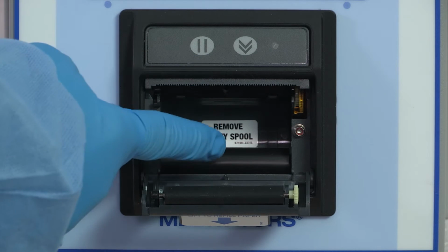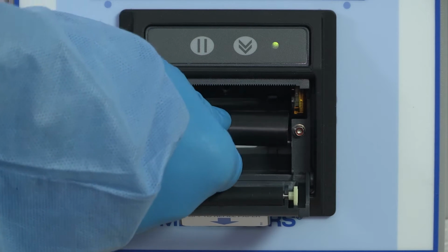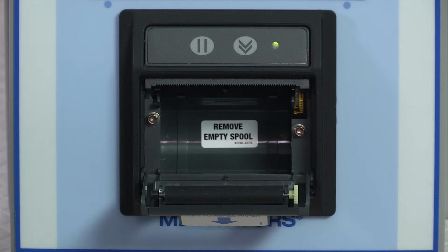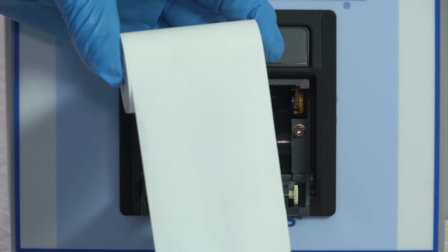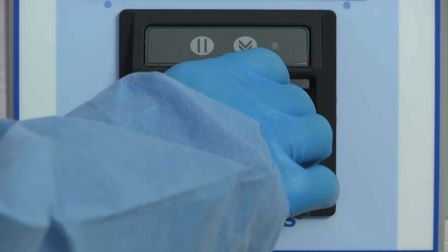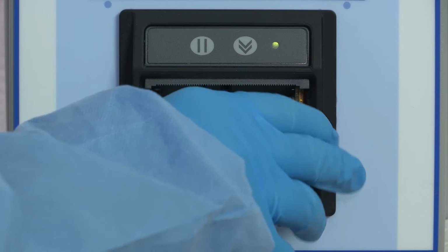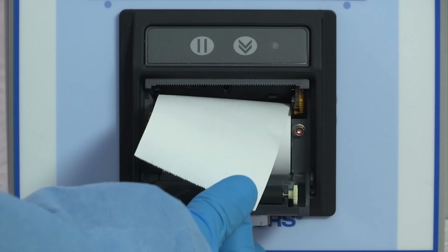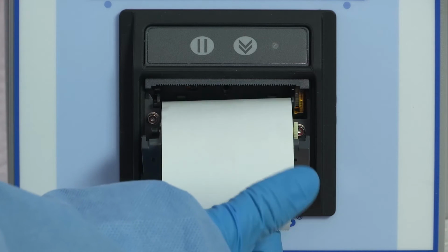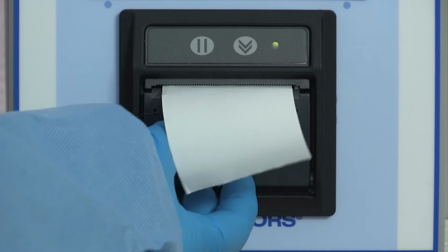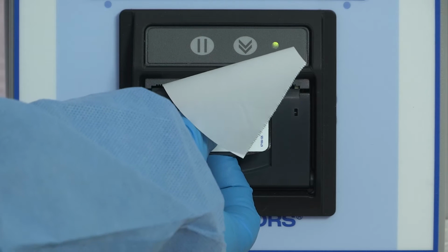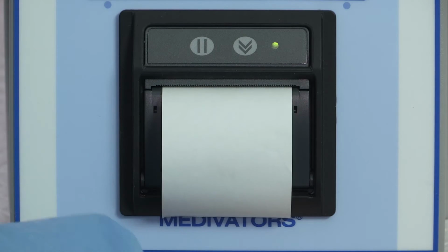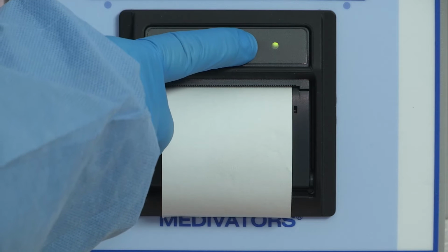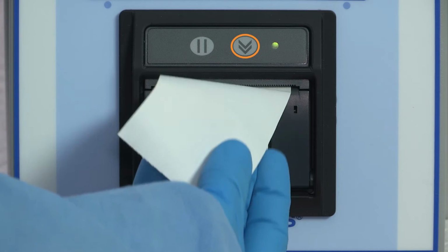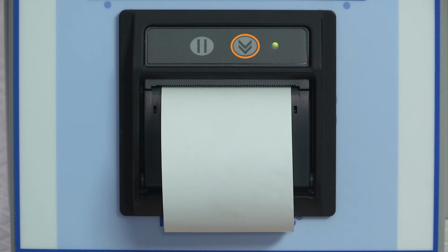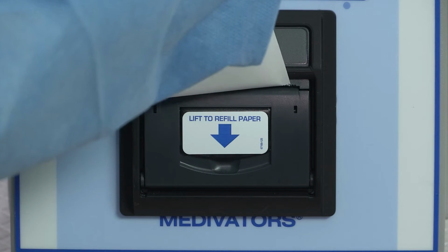With the printer access door open, remove the empty paper spool and discard. Locate a new paper roll and unreel approximately 1/2 inch of paper. Place the new paper roll in the printer paper compartment with the leading edge of the paper coming off the top of the paper roll. Close the printer paper access door by applying a small amount of pressure onto the front of the door, ensuring that the lid clicks into the lock position. If it is necessary to advance the paper forward, press the Paper Feed button, the double down arrows located on the printer front. Tear off the excess paper by pulling up against the serrated edge.